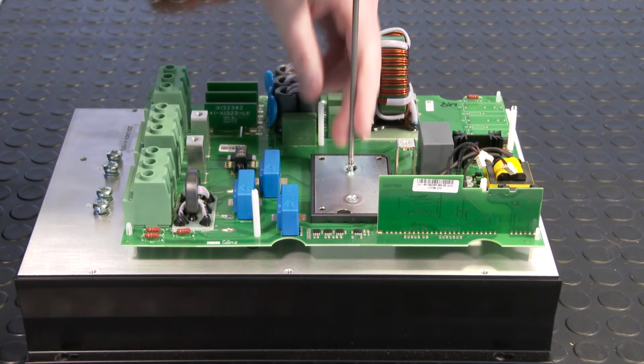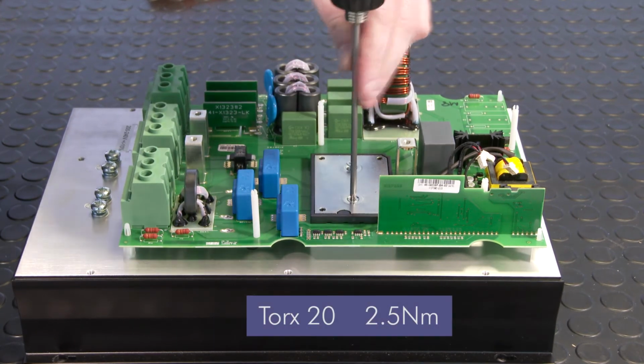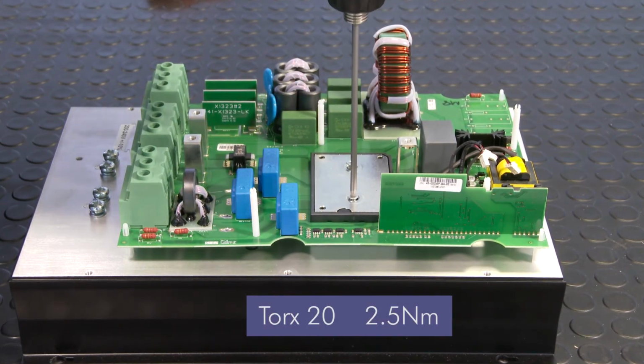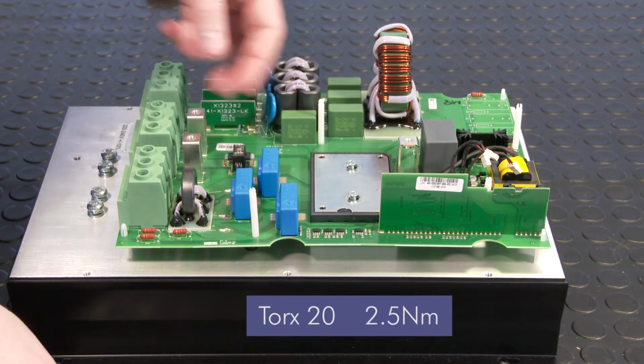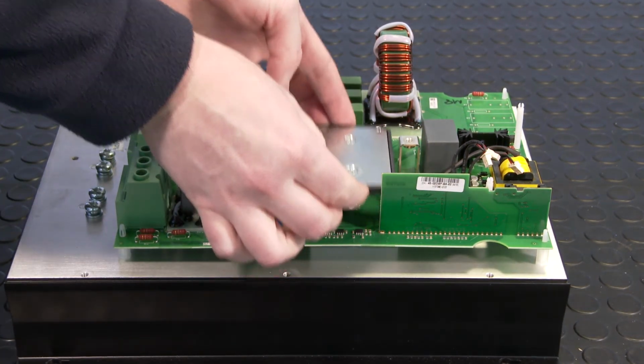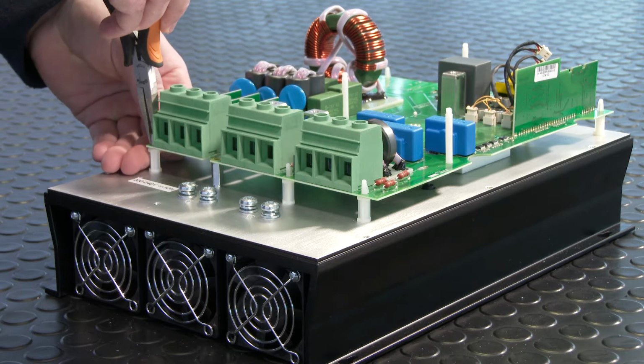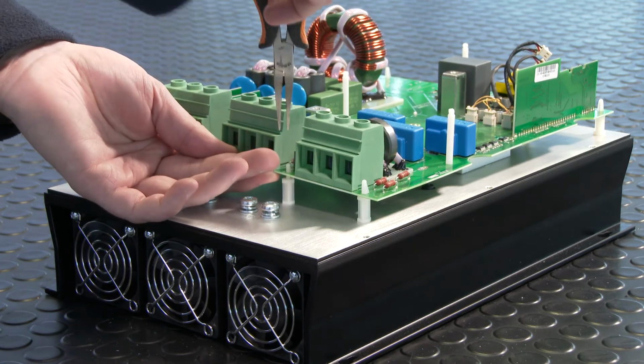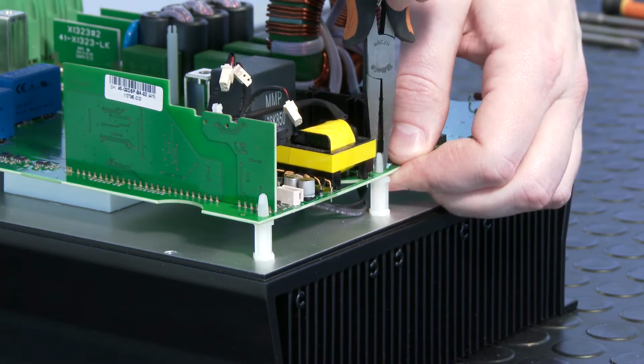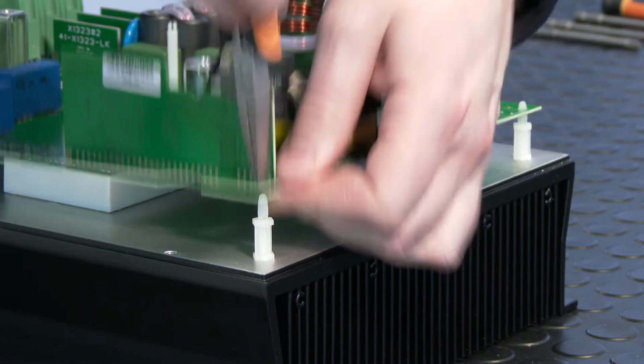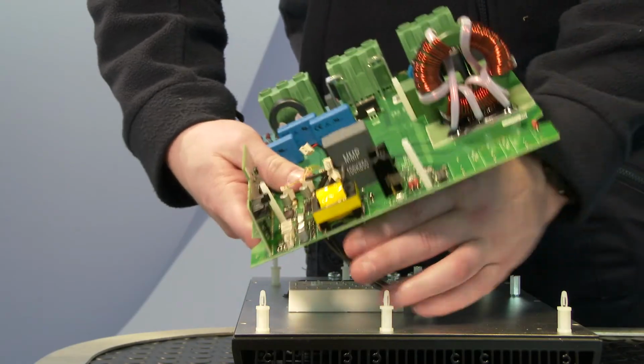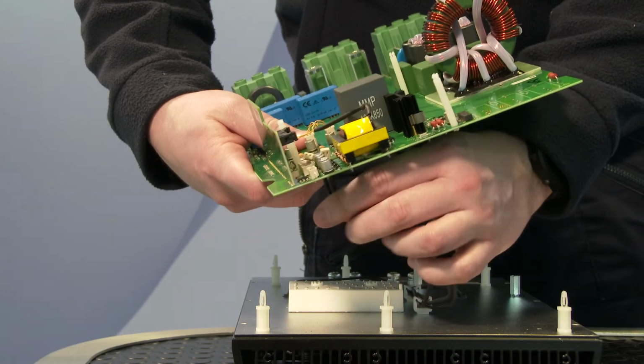Use a Torx 20 screwdriver to remove the 2 power module top plate screws and lift the top plate away. The torque setting is 2.5 Nm. Using long nose pliers, unclip the 6 plastic pillars from the PCB and lift it away, making sure the power module stays in place and the power board is placed on a clean surface.